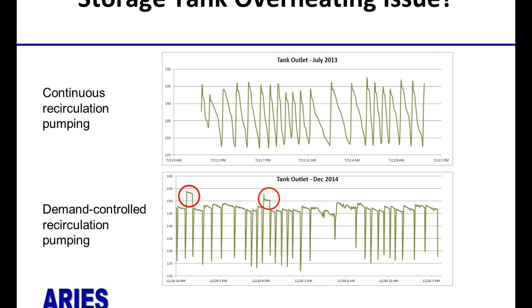And the issue here is that because the aquastat is placed fairly far down the tank, it might sense cooler temperatures with demand-controlled pump and call for the boiler to run, and the boiler might send hot water to the top of the tank where it could short-circuit across and go up to the tenants. And we've circled two parts on the plot here which may show that this is happening, but we're going to be looking more at this in the future in our next project that Jordan's going to talk about shortly, and confirm whether this is a prevalent thing or if this is just a one-off.